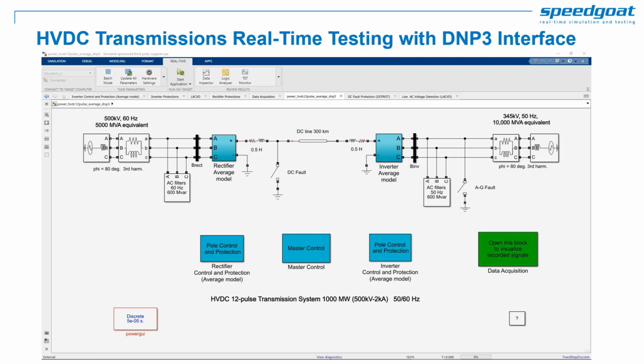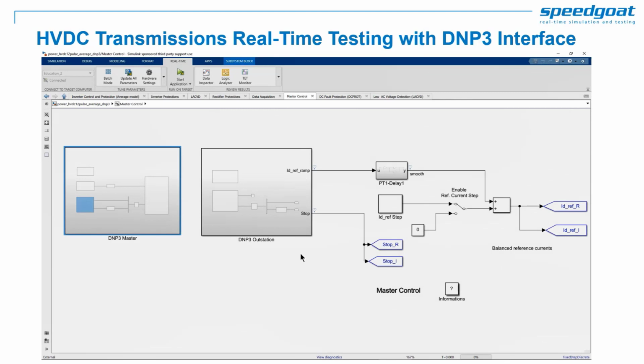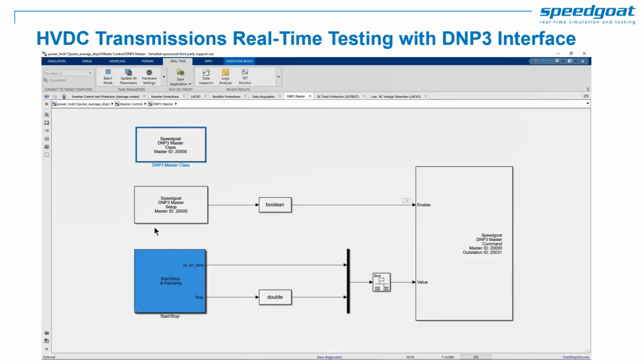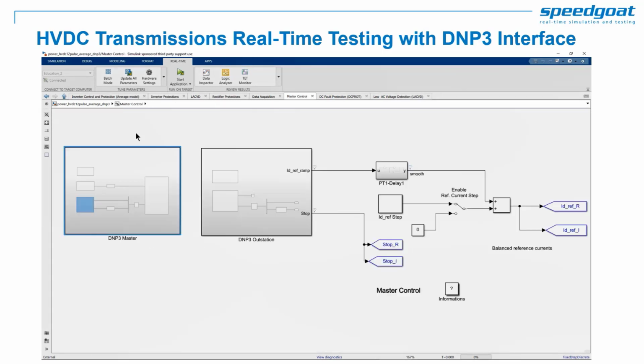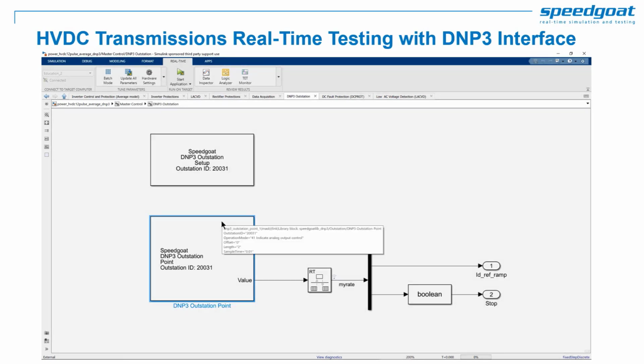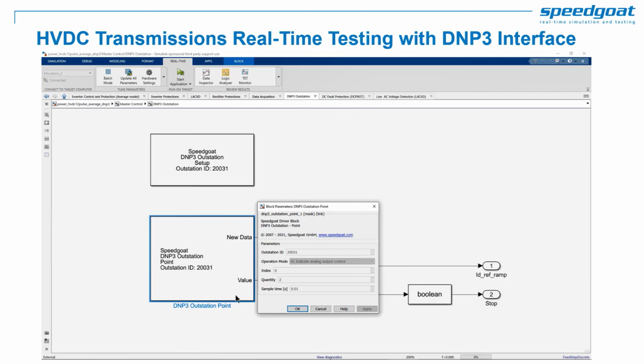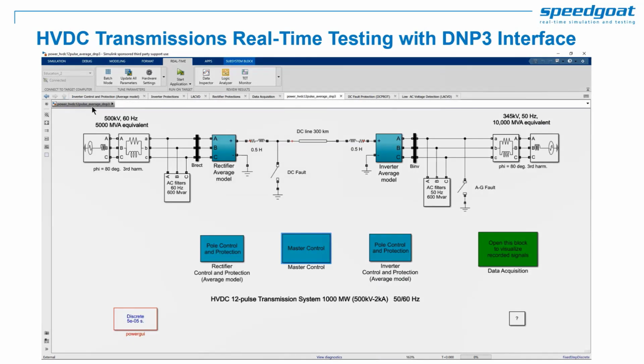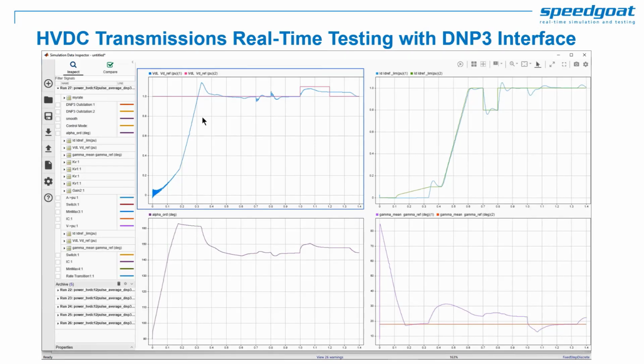Let's look at an HVDC model with all levels of controls. We have rectifier and inverter primary and secondary controls and a master control. We loop back the master control with DNP3. The output of the master control is sent via a DNP3 master. On the other end, we have modeled a DNP3 outstation capturing data coming from the DNP3 master. We ran this loopback test in real time. Let's run it, and with this, we can validate the DNP3 communication. We can inspect simulation results and see that the operating points are sent successfully by the master control via DNP3, and that the primary and secondary controls regulate the grid voltages and currents accordingly.